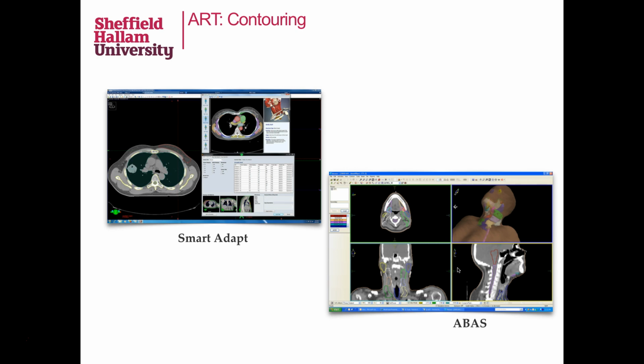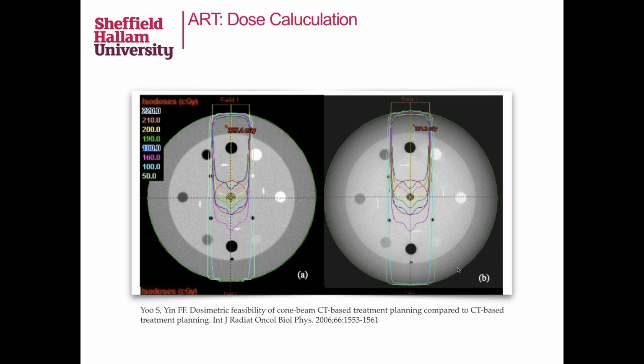We then want to calculate the dose. So traditionally we carry out some phantom testing on our CT scanner in order to calibrate our profiles in order to calculate the dose. Sorry, I said that on our Linac, I meant on our CT scanner. So we might use a phantom like this to do that, and actually there's no reason why we can't do that on a cone beam scanner and change the electron densities in our profiles.